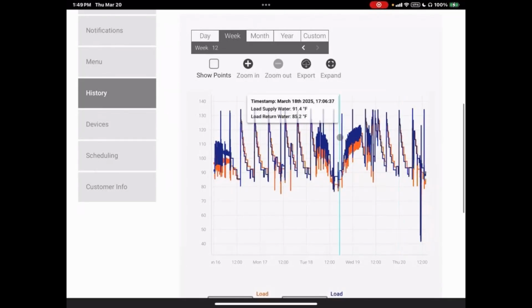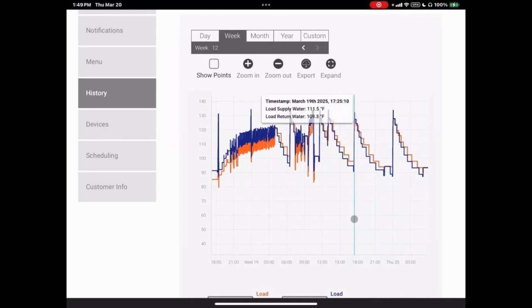Let me do this. Okay. So where you see this, you can see this hot water call and that it happened relatively quickly, and then we just have this tapering down, stair-stepped. This means that the unit wasn't running, and this is just the water cooling off, just via standing losses, that's in the heat exchanger and in the pipes. But you can see on what kind of intervals we had hot water calls, where we see this kind of thick line. This is where the unit was heating the space. So we were going along heating the space. We got a domestic hot water call, and then that call ended, and then we went back to heating the space again. You can see that these hot water calls are very, very brief in time.